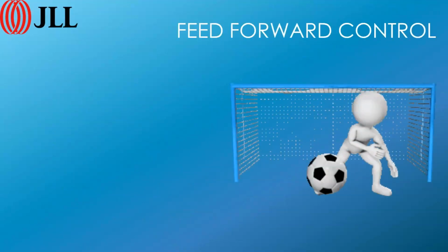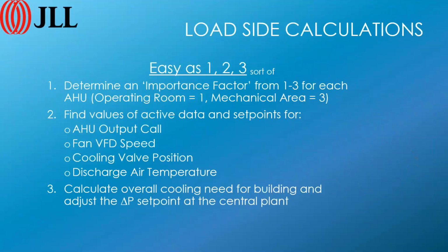And that adjustment has to take that change in plant chiller load, plant cooling load, into account. Okay. That is absolutely the case. And the control loop has to do that. It has to take that into account. Okay. And that is a commissioning function. That is truly a commissioning function.